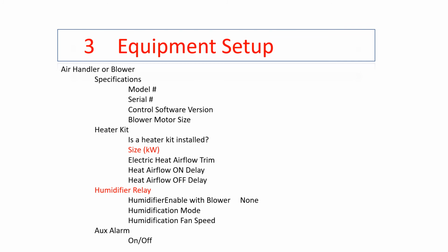If you have an air handler or blower, we'll have to go in and go to the heater kit, and tell it we have a heater kit and what size the heater kit is. We can set our electric heat trim and our delays on electric heat. We also have a humidifier relay, which is new to the FEC air handler. You will not see this on the PEC, but you will on the FEC. You can enable the humidifier relay with blower or humidification mode and fan speed. So with blower, it will operate when the blower's on. With humidification mode, it'll force the blower on. That's something you want to use on, let's say, a steam humidifier.